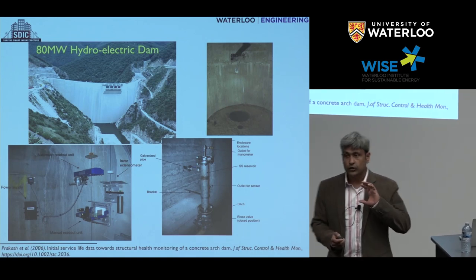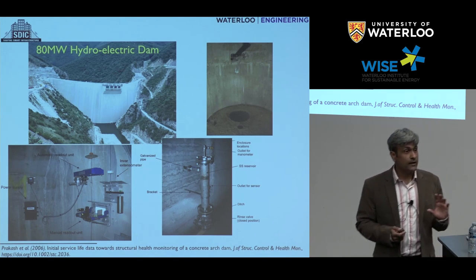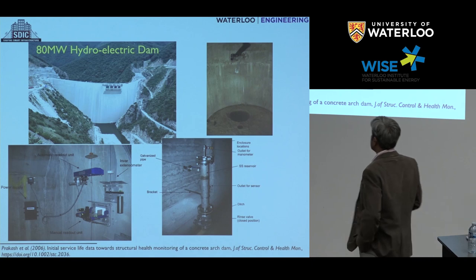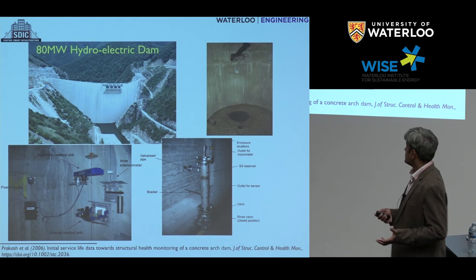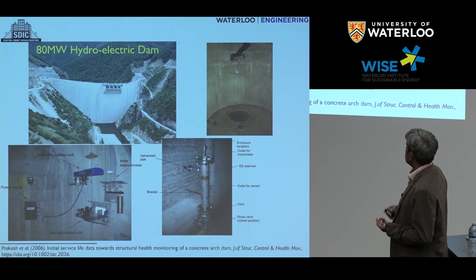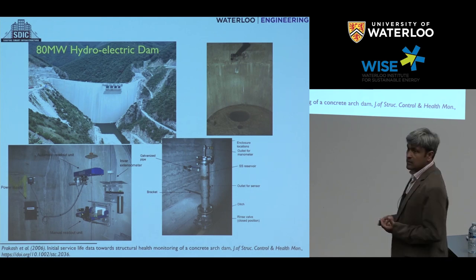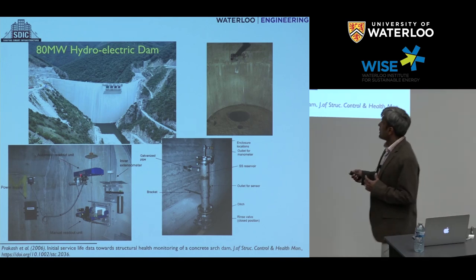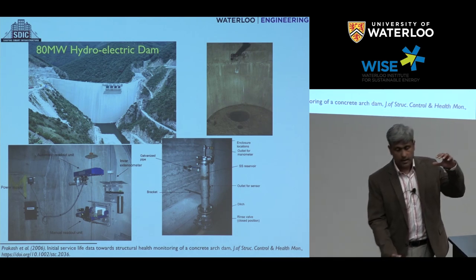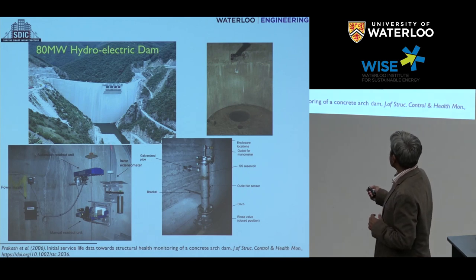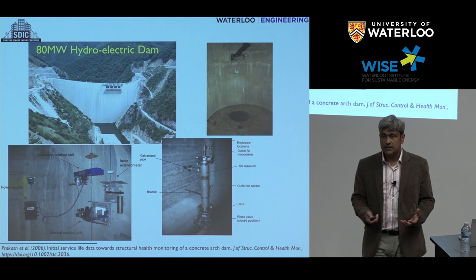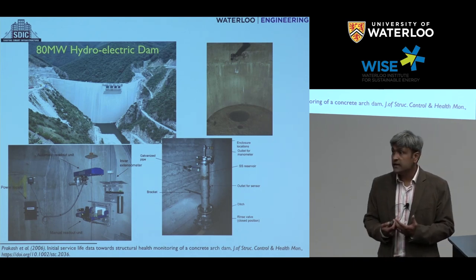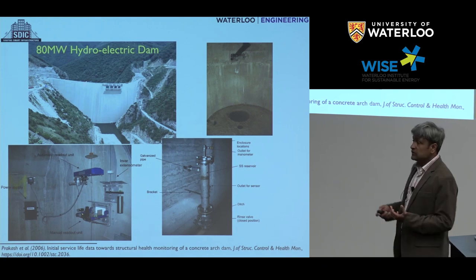Before we understand what we can do with it, we should understand what we are doing with it currently. Here's a project we worked on — a dam in Bulgaria, around 2016. This is an 80-megawatt hydroelectric dam that has all sorts of sensors measuring all sorts of things: extensometers telling you how much a section of the dam is expanding or contracting, borehole sensors for soil pressures, inclinometers, strain gauges — hundreds and hundreds of devices currently measuring all sorts of parameters within this dam.